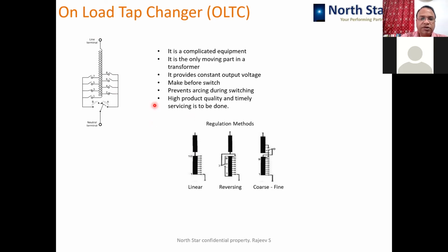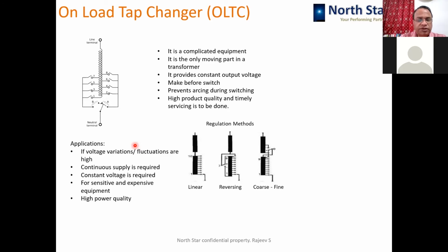Okay, so it prevents arcing during switching. But it is not eliminating the arcing, because when switching is happening there is a high resistor, which is called a dynamic resistance, that comes in the circuit, and that causes increasing of the resistance and lowering of the current. So that way you are providing a parallel path, and that's how the continuity of the supply is maintained even when the voltage is being adjusted by operating the OLTC. So you can see that this is a complex mechanism, which is causing some kind of disturbances, like arcing does happen. It is not perfectly arcing proof. Okay, so the more the number of operations, the more is the arcing in the OLTC chamber, and the pitting of the contacts and damage of the moving and fixed contacts happen.